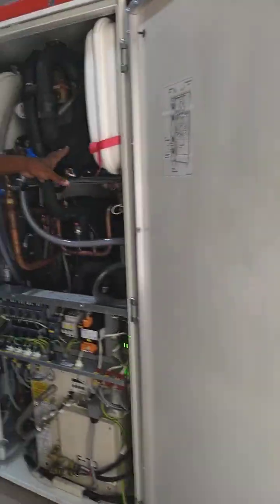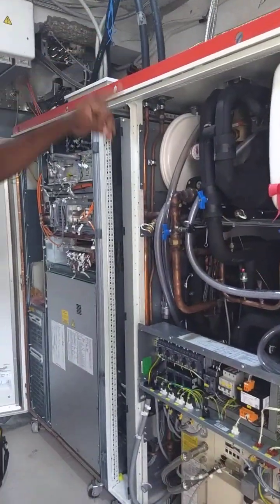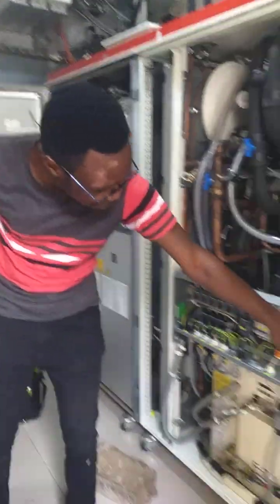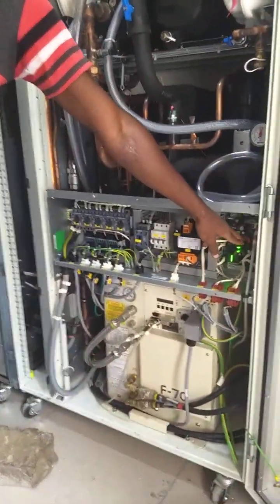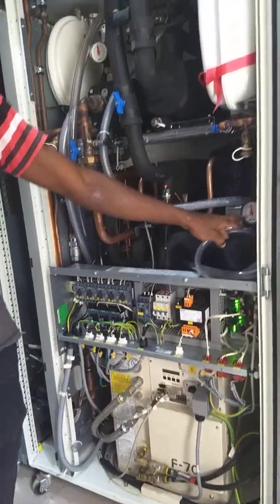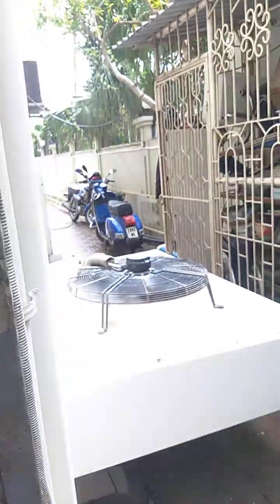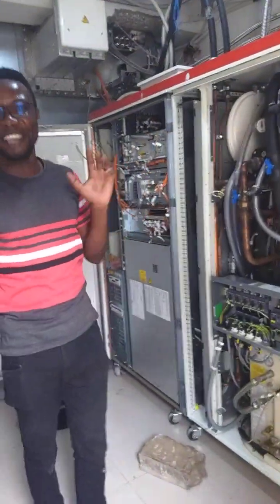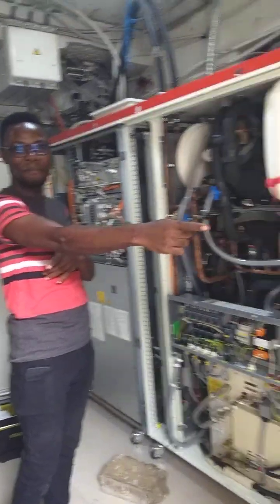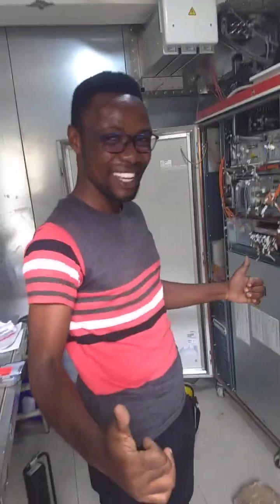Until the pump is on, that one will not be on. You can see the temperature was 25. Now it's coming down. Now the pump is on. The fan is on. This is the only thing for the MRI engineer. If that one doesn't come on, then you are in trouble, and you ask why it is not coming on. So success. Two thumbs up.